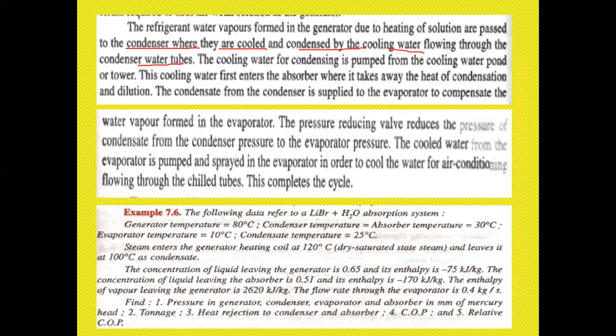Now the condensate from the condenser is supplied to the evaporator to compensate for the water vapor formed in the evaporator. The pressure reducing valve reduces the pressure from the condenser pressure to the evaporator pressure. Now the cooled water from the evaporator is pumped and sprayed in the evaporator in order to cool the water for air conditioning flowing through the chilled tubes. This completes the cycle. So what is the last point? The cooled water from the evaporator is pumped and sprayed in the evaporator.